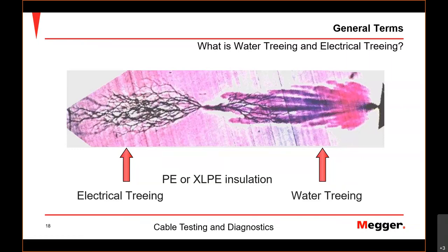And this arcing, this is the electrical tree, and that will burn through at operating voltage in 1 or 2 days, at our test voltage in 60 minutes. We go with higher voltage, so they grow faster, and laboratory tests show 60 minutes is what they take. If in 60 minutes a water tree hasn't blown up, it is because there was no water tree there. The water tree was maybe much smaller, not critical yet, so it didn't even convert into an electrical tree. This part here, this cloud, this electrical tree takes 60 minutes.